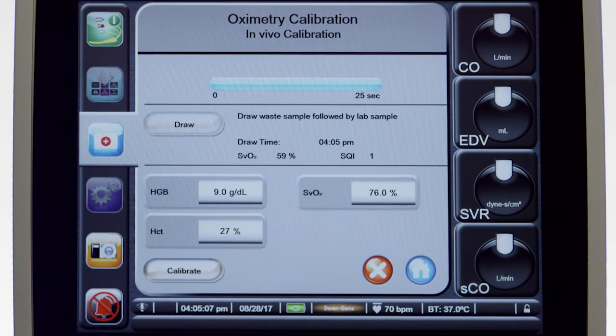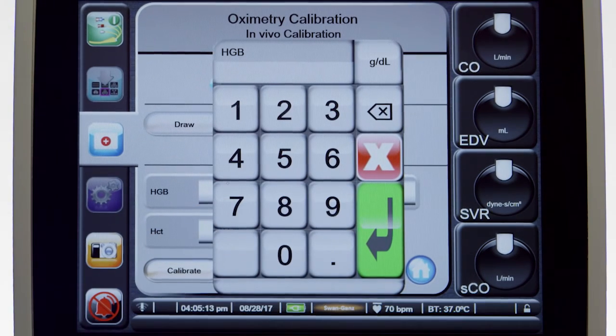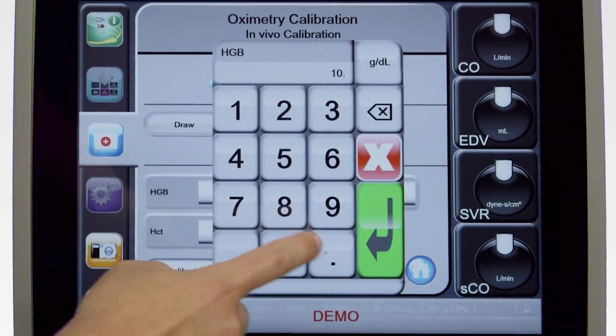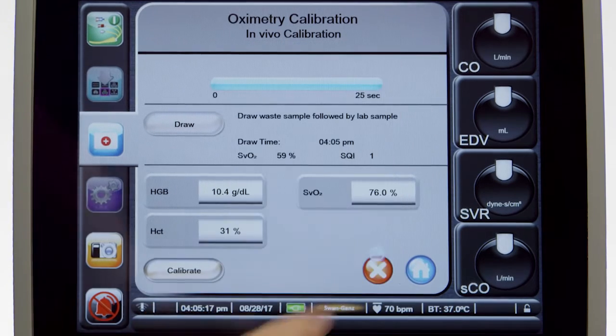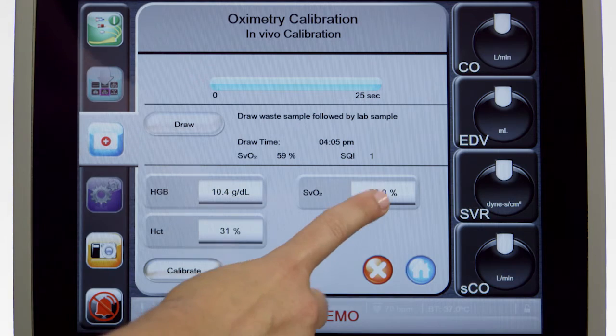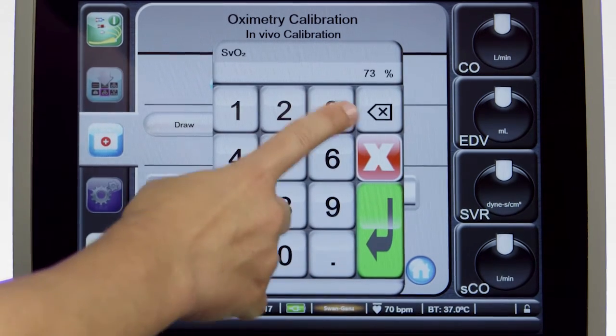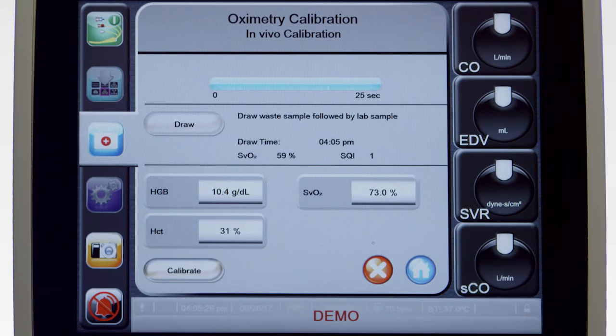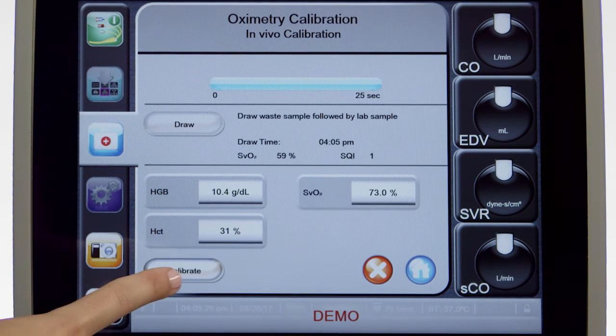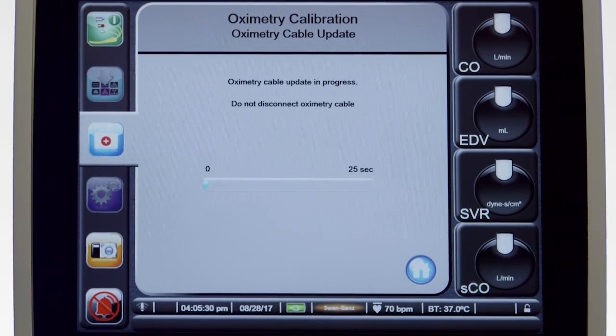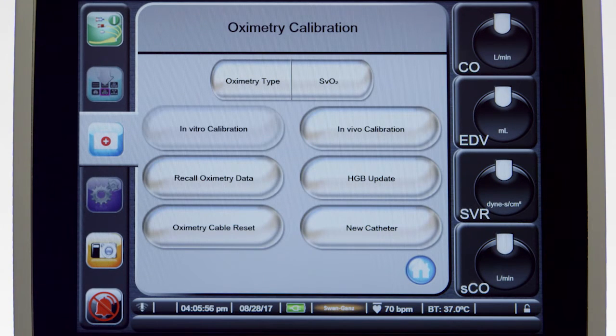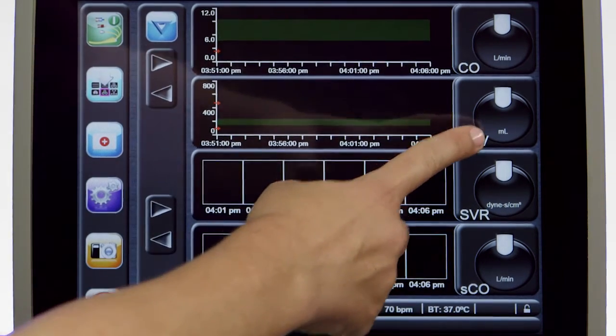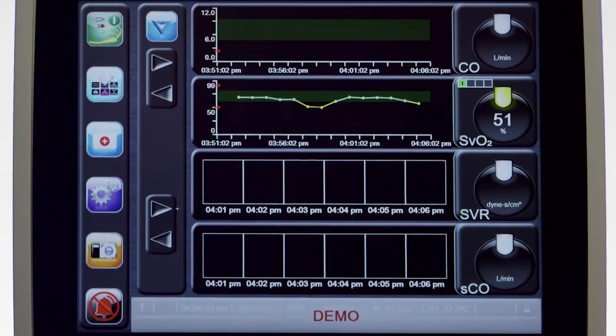Once you have the lab results, enter your patient's hemoglobin or hematocrit values. When you enter one of the parameters, the other will be calculated for you. Also enter your patient's SVO2 values. Touch the Calibrate button to perform in vivo calibration. After 25 seconds, the calibration will be complete, and the new SVO2 value will update every 2 seconds. Touch the Home icon to return to the main monitoring screen.